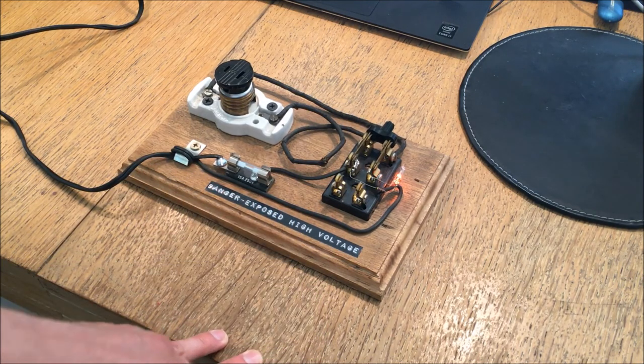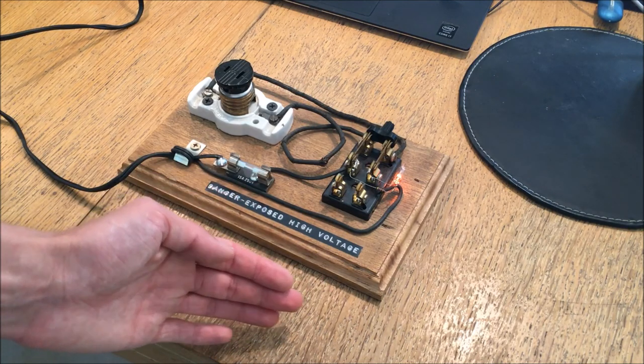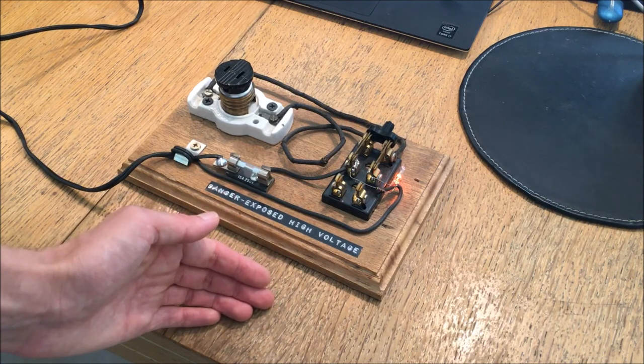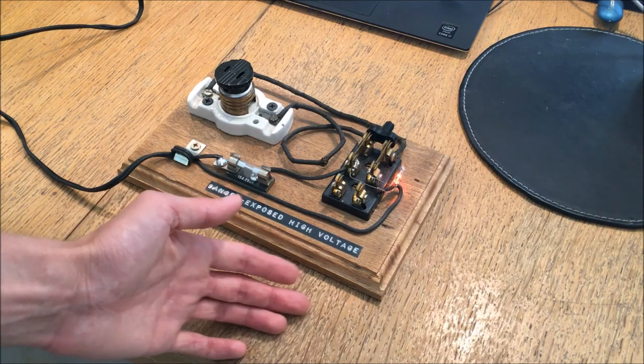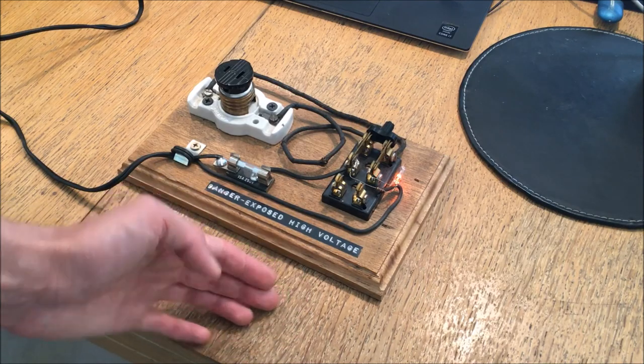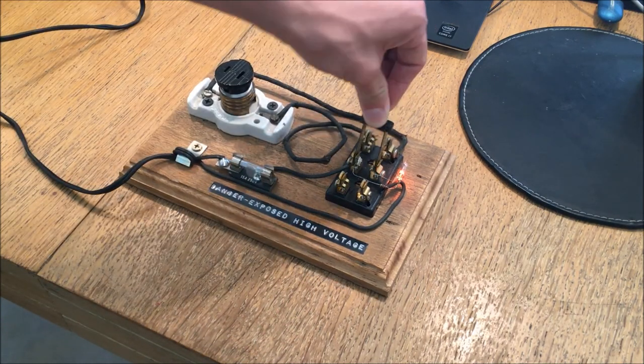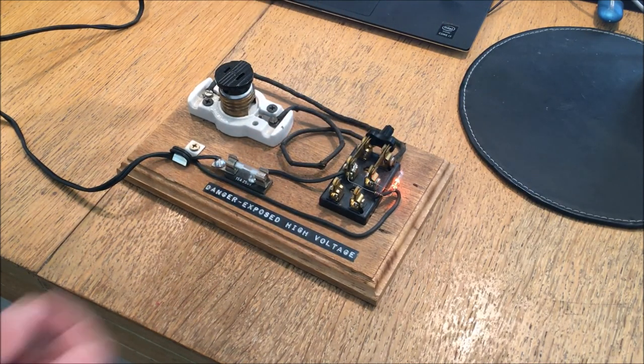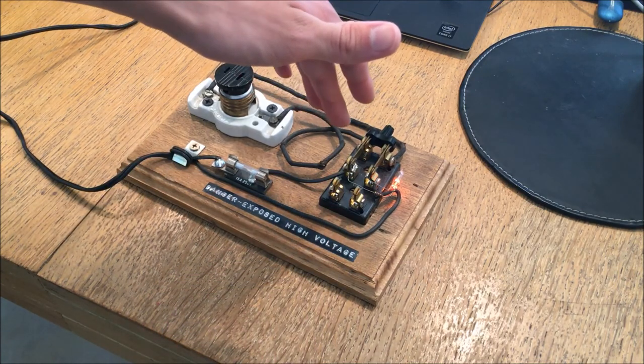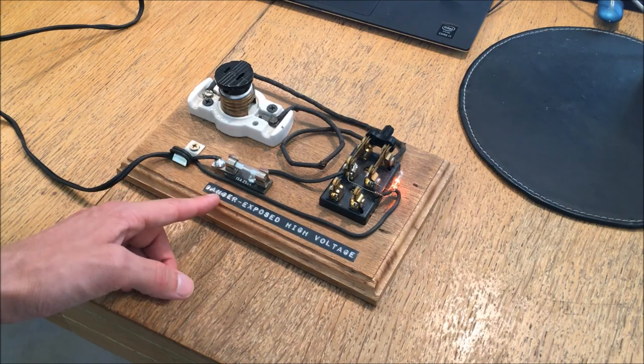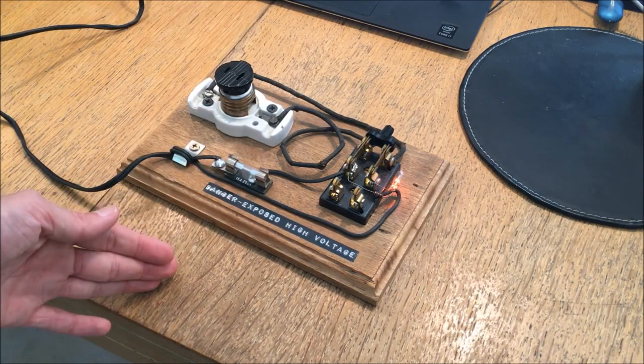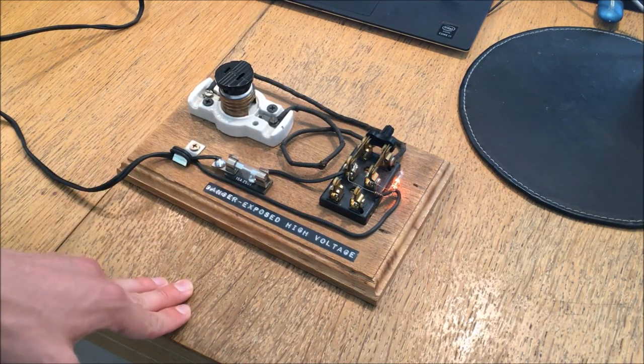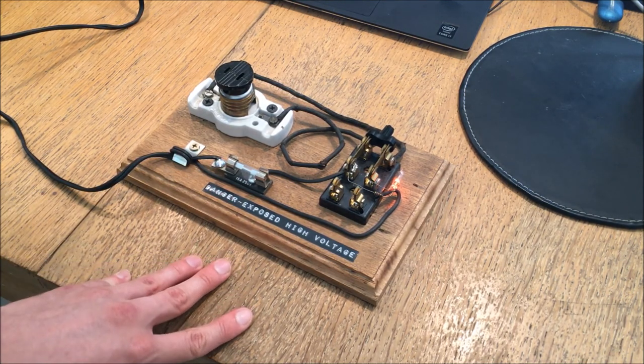That's going to lead into another thing that I'm going to discuss as well which is if you're working on multiple wires that are hanging loosely in a circuit be sure and only manipulate one wire at a time. If it's live you want to make sure that it has no chance or at least as little chance as possible of contacting something that's grounded or otherwise at reference potential to that cable. If I'm connecting something or turning on and off this switch I want to make sure that I'm not doing two things at once where another wire could fall down onto that switch and cause a short circuit. Now this is a fused board, I have a 15 amp fuse here, but nevertheless it would still create a big flash and would not be ideal if a short circuit were to occur.